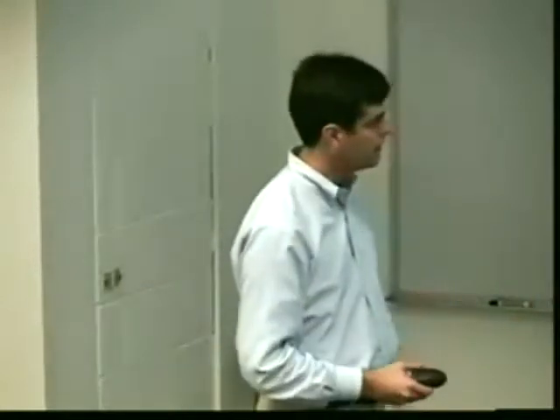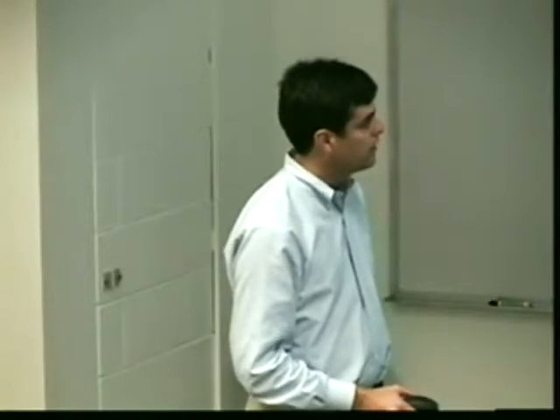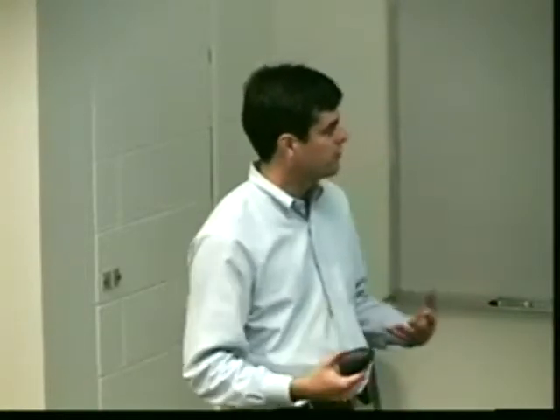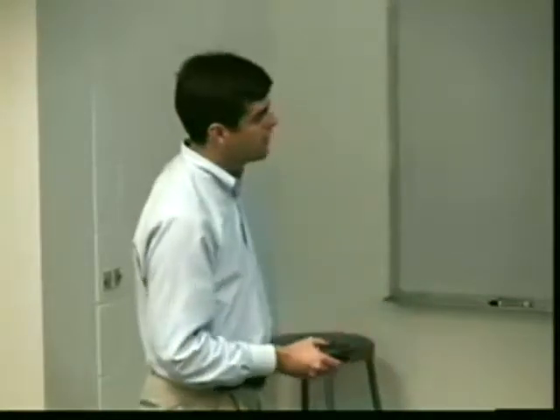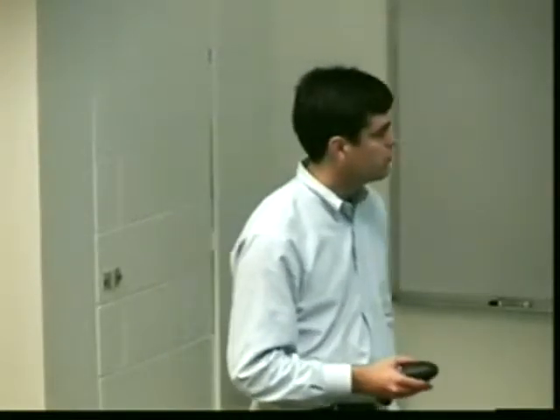This one also has the possibility of adding a small angle scattering detector so that at the same time you're probing lattice spacings, which is a sort of small length scale thing, you can study microstructure to look at grain boundary effects and so forth in the SANS, and you can do that in situ, so you can put on load frames and furnaces and that sort of stuff. It's a very fast diffractometer, so you can do kinetic behavior. In principle, we could do single pulse diffraction, which means you get a pattern every 16.7 milliseconds.